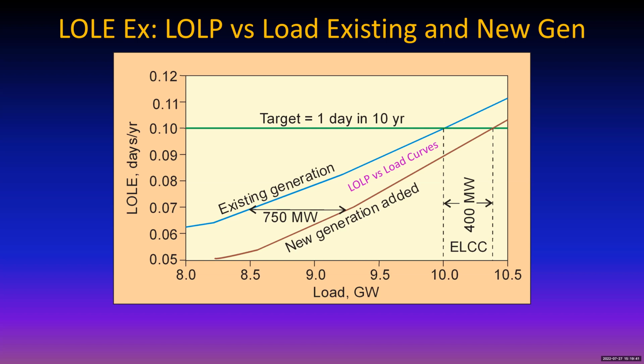So bottom line is, if you add new generation, you can't just add 400 megawatts and expect that'll solve the problem. You're probably going to have to add closer to 800 megawatts in order to meet your LOLE requirement of 1 day in 10 years.